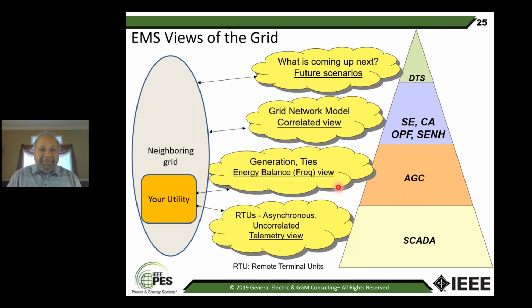These are asynchronous, uncorrelated—I call this a telemetry view. Then we also have the energy balance view, where you're looking at generation-load imbalance, making sure frequency stays close to normal, done by AGC. Then you have a grid network model, a correlated view, where you look at your utility as well as the neighboring grid, because a disturbance on your utility can cause electricity to flow through the neighboring grid. So you have to model any relevant portions of your neighbors which affect your grid.